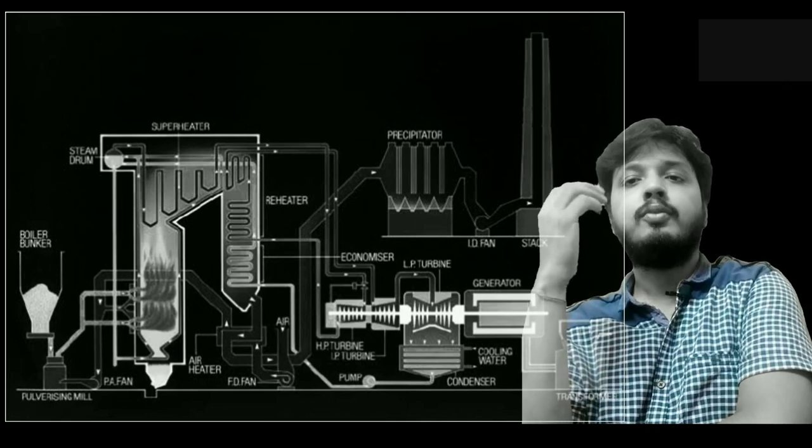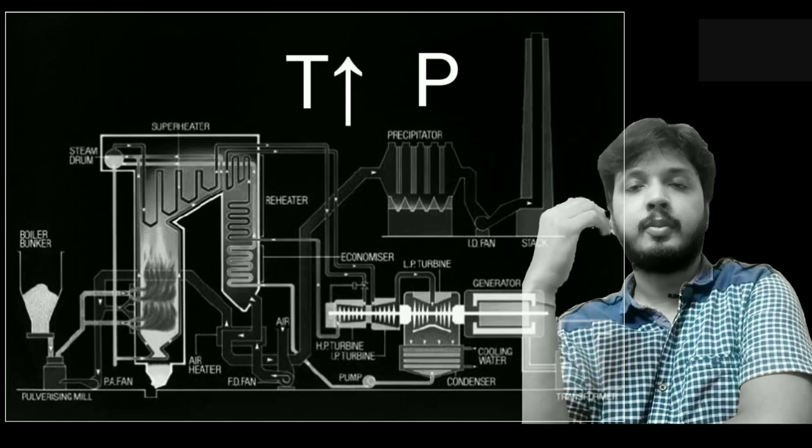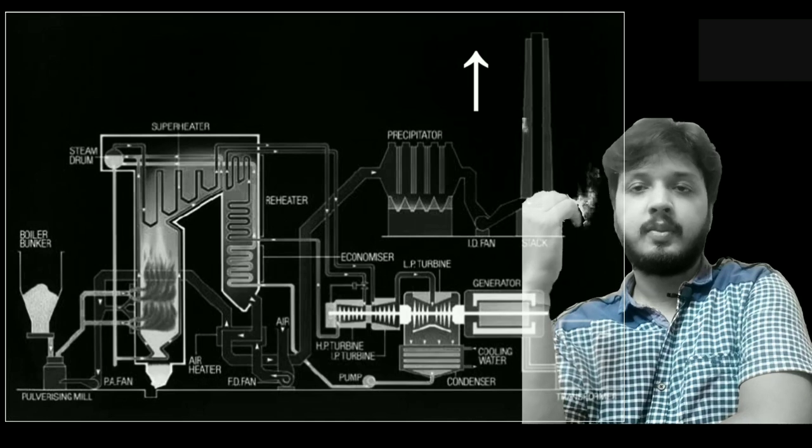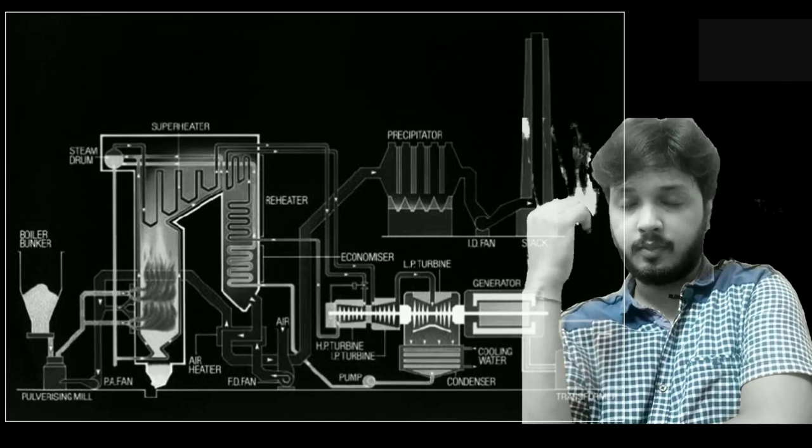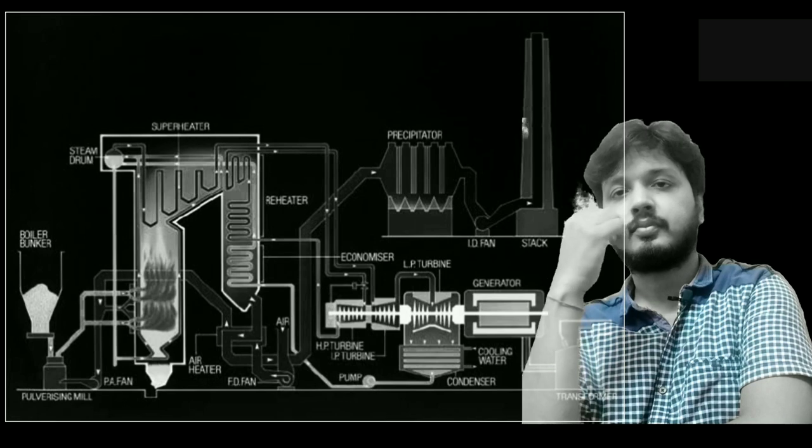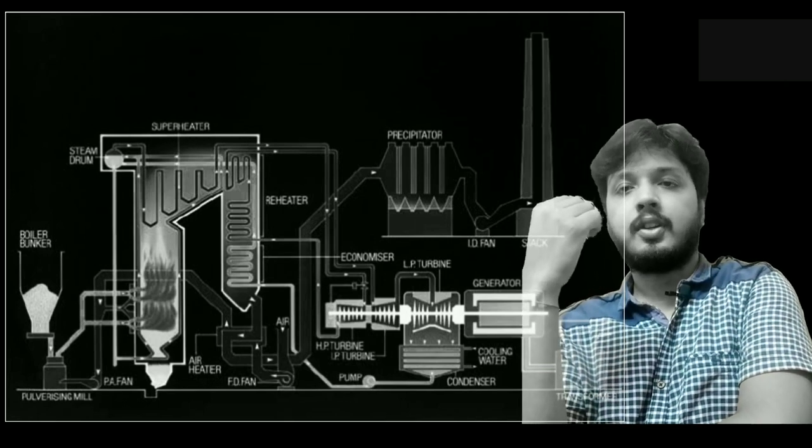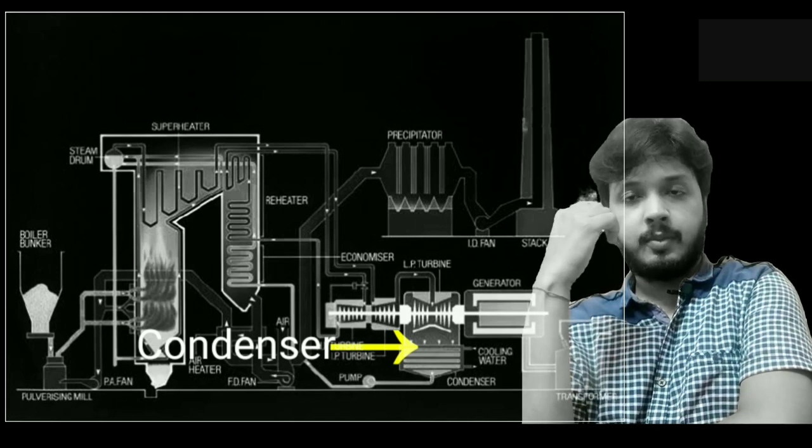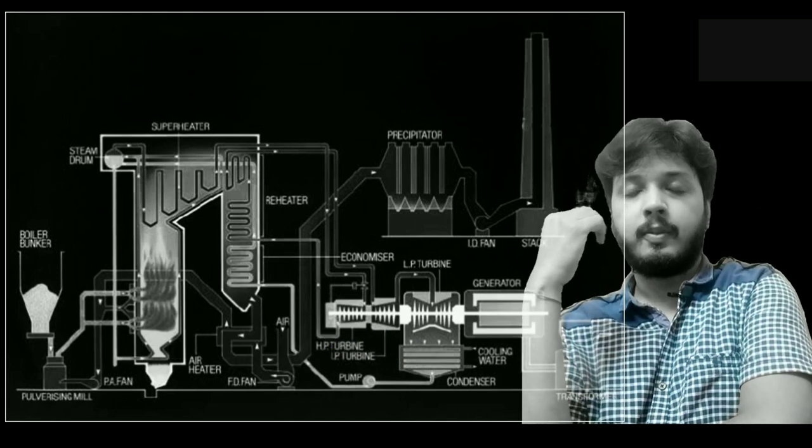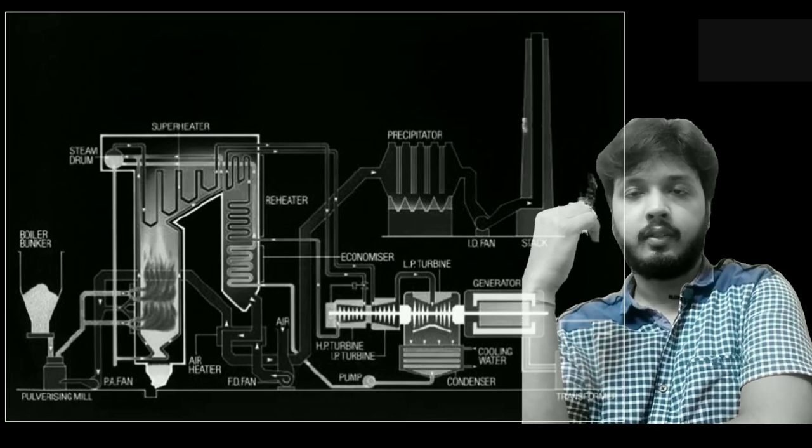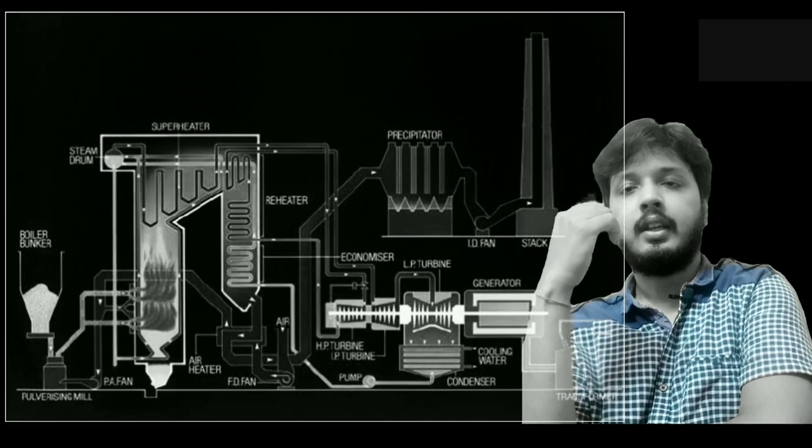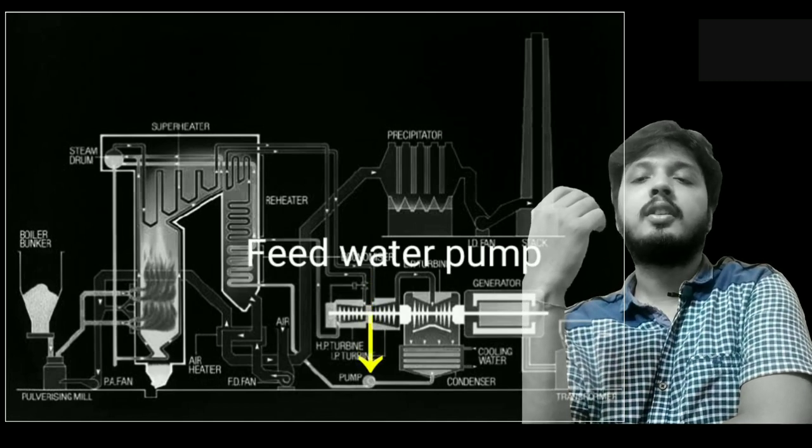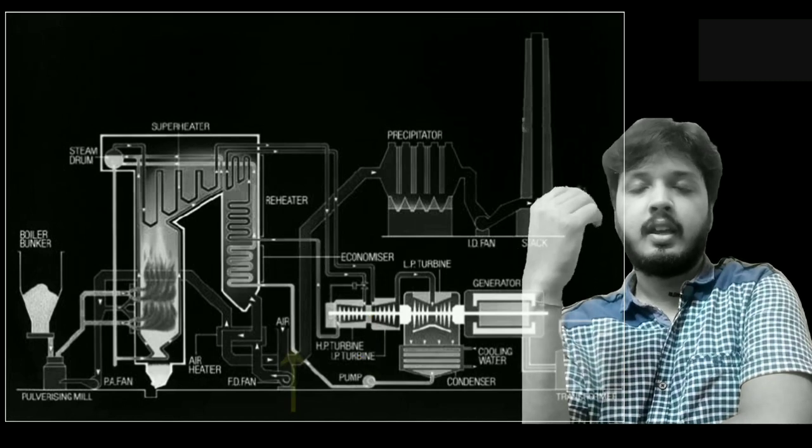If we want to reuse the steam, we have to increase the temperature and the pressure of the steam again. Because after passing through the turbine blades, the temperature and pressure of the steam decreases. To increase the pressure and temperature, first we pass it through a condenser. In the condenser, coming in contact with the cold water pipe, the steam condenses to water. The steam releases latent heat and becomes water. This water is fed to the feed water pump. The feed water pump increases the pressure of the water and sends it to the boiler.